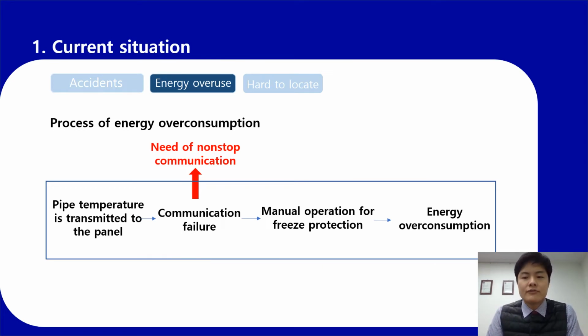Then, for freeze protection, the manager has no other option but to manually turn on the heating cable continuously. In this case, in the winter season, up to 3 times more power can be unnecessarily overused. To prevent the energy overconsumption, non-stop communication that transmits the temperature information to the panel is very important.